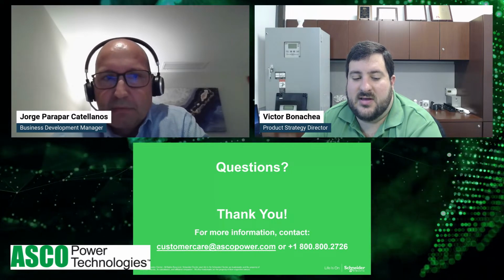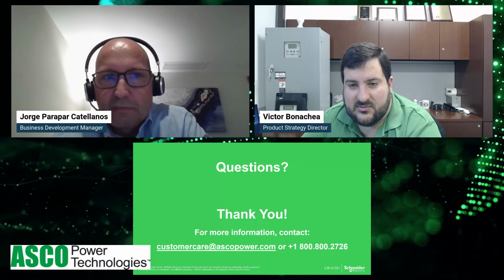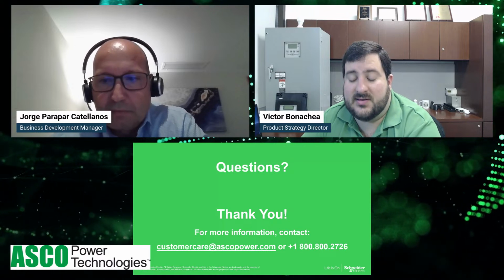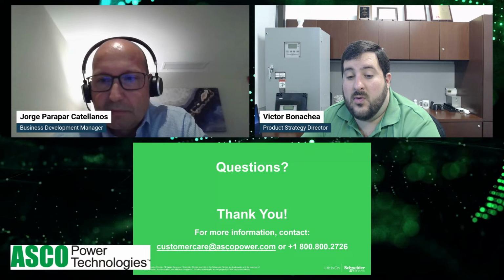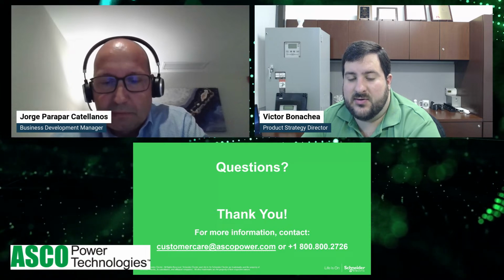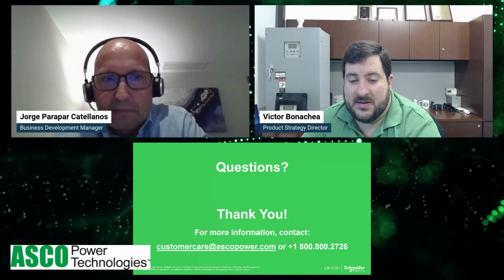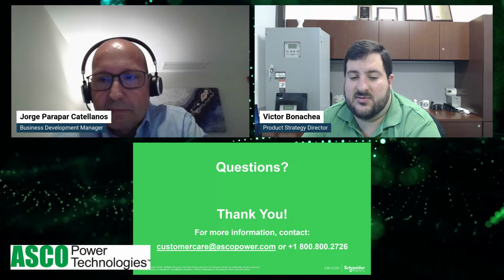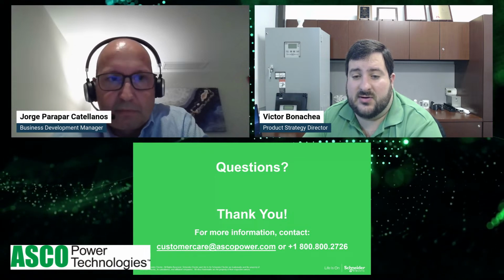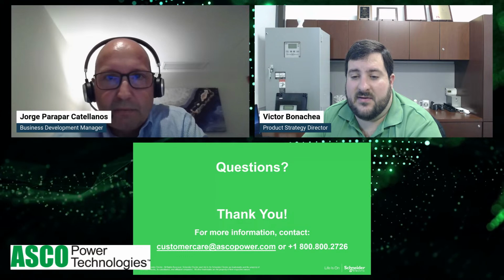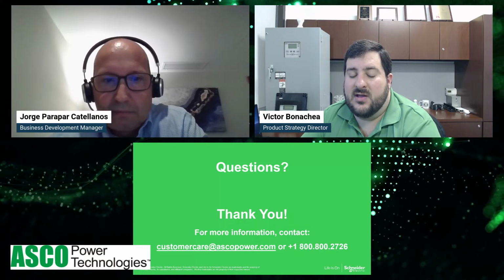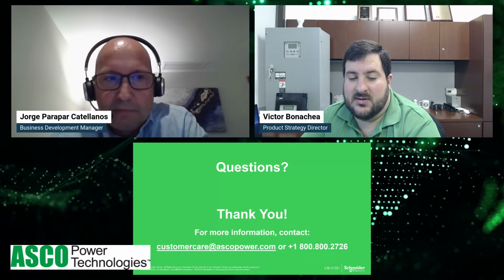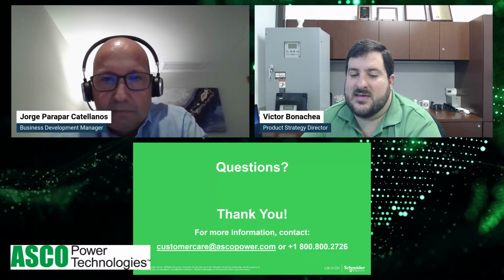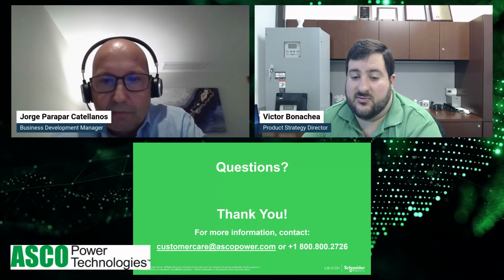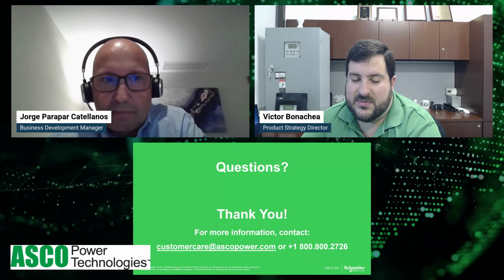As I mentioned, a delayed transition transfer switch can be used to disconnect from one source, wait a period of time for the large motor or pump to stop spinning and lose all its momentum and residual energy before connecting it to another source, making it a very safe, effective transfer and very predictable. That avoids any transients that may happen from the motor connecting to a source that it's no longer synchronized to.